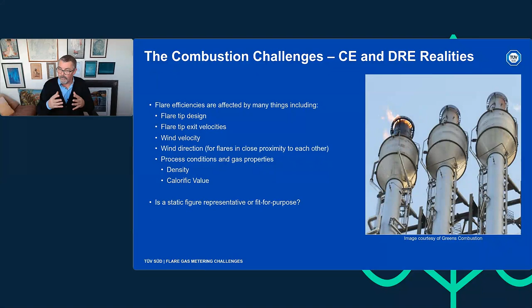I have an image here of a flare that's been CFD modelled, and at the moment, on a still day, 3 metre per second wind, the combustion efficiency and the destruction and removal efficiency for methane are both very, very close to 100%. If I keep everything the same, except the wind speed, and I have a windy day or even a very stormy day, we can see that it significantly impacts the efficiency of the flare. And on the right-hand side example, 97.7%, we're now below the assumed 98%. So sometimes we're way above the 98%, and sometimes we're below the 98%. So I question the validity of a static figure as the guidelines and the regulations become more sophisticated.